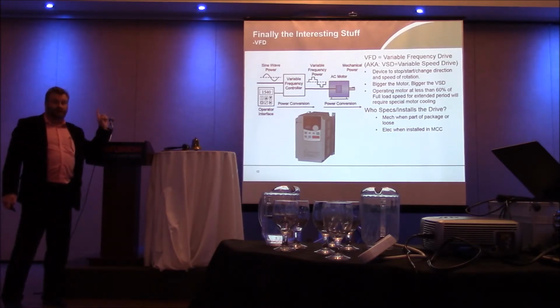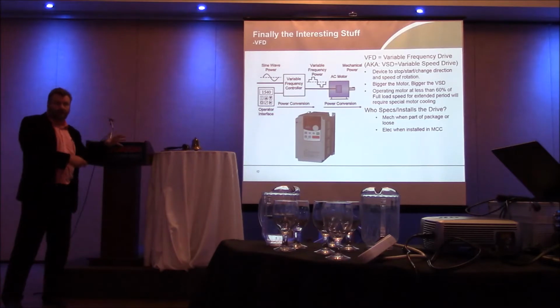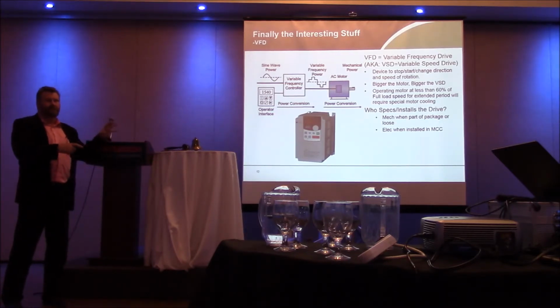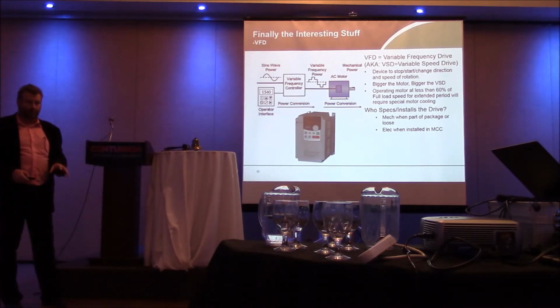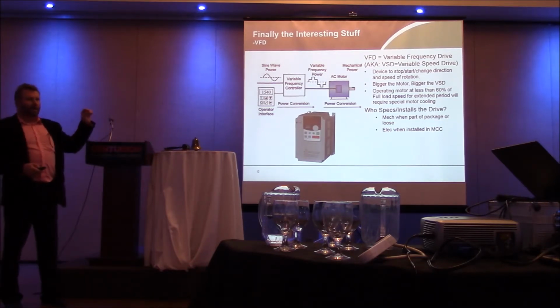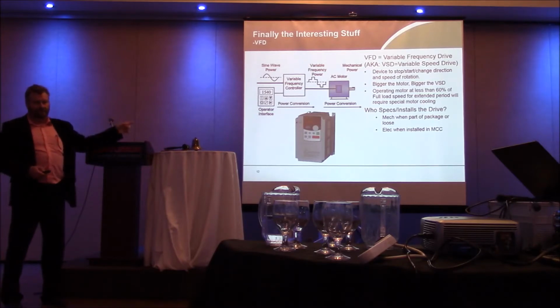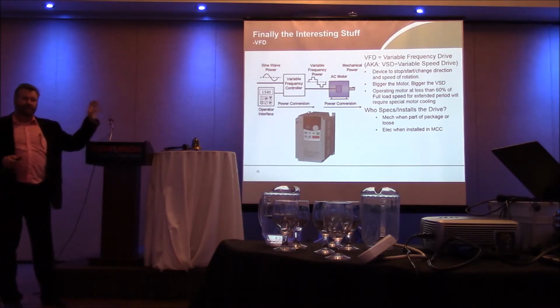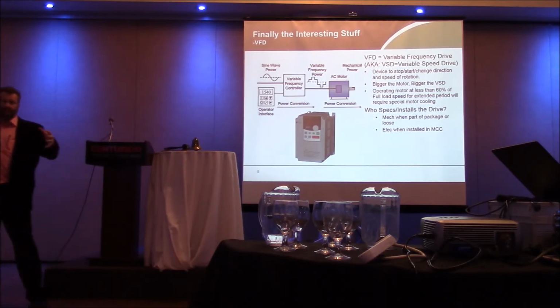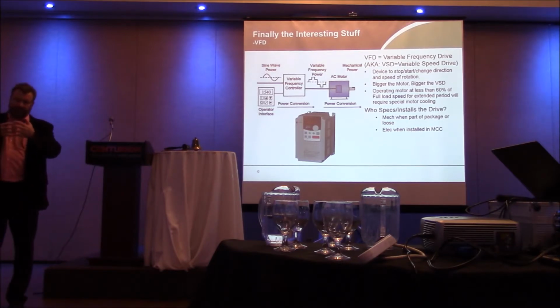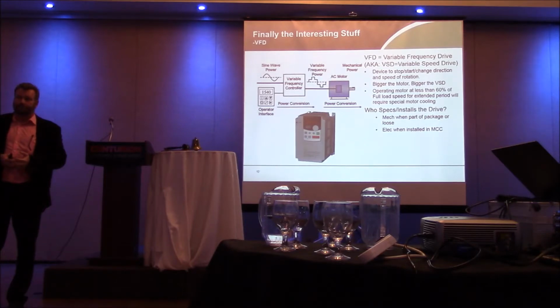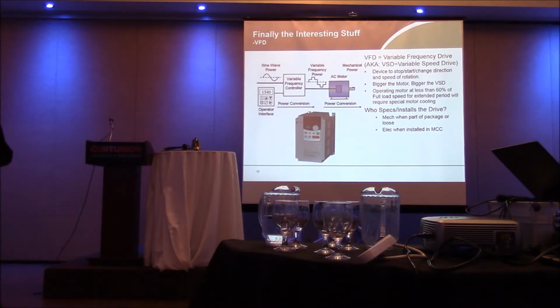When it's installed inside our motor control center, and the drive is put inside the motor control center, the integration with electrical has to be huge. And I've done this, I do this, and I hate it because it just never seems to work out right unless you get the equipment manufacturer and the MCC manufacturer really tightly engaged with each other at shop drawing time. I always seem to have trouble with this.